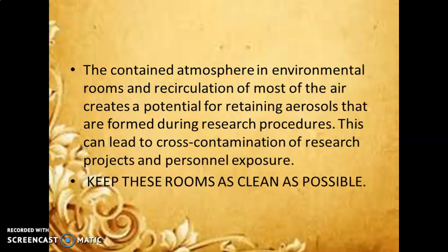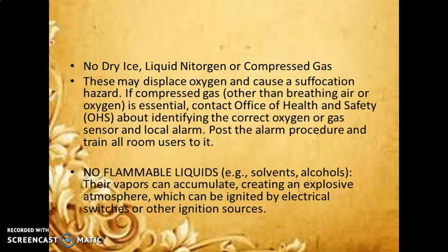The contained atmosphere in the environmental room and the recirculation of most of the air creates a potential for retaining aerosols that are formed during research procedures. This can lead to cross-contamination of the research projects and personal exposure. So, keep these rooms as clean as possible. No dry ice, liquid nitrogen or compressed gas in the cold room. This may displace oxygen and may cause a suffocation hazard. If compressed gases other than breathing air or oxygen are essential, contact the Office of Health and Safety (OHS) about identifying the correct oxygen or gas sensor and local alarm. Post the alarm procedure and train all the room users in it.